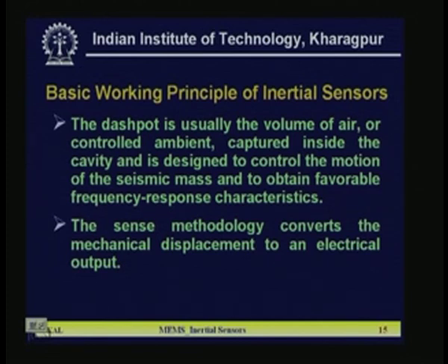If damping is not there, what will happen? The spring is holding the proof mass. When it starts vibrating, it will stop only after infinite time. It oscillates, so there has to be some damping arrangement, so that the oscillation dies out and it comes to rest within a very short time. For that requirement you have to have a damping arrangement, and that is done with the help of the dashpot configuration. In the dashpot configuration, basically the gap between the proof mass and the top and bottom layer, and the density and pressure of the gas used in these small cavities at the top and bottom of the proof mass along with the flexure, determine the damping.